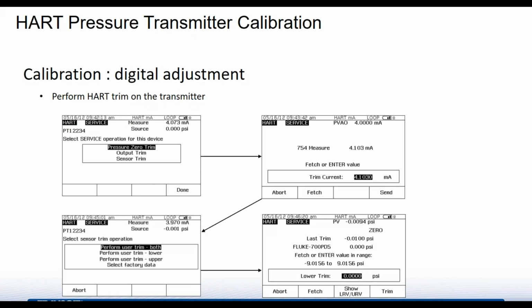With HART, you can do the trim for your input sensor and your output milliamp. You can do that digitally with HART. If you had an analog transmitter, of course, you'd have your 0-100% span adjustments that you'd be doing with a screwdriver, but this is a lot more accurate. So with the calibrator, you can go in and do your output trim for 4-20, and verify what the transmitter thinks it's putting out. Here's the PV AO: it thinks it's putting out 4, but this 4 in this case is measuring 4.1, so it's out of spec.